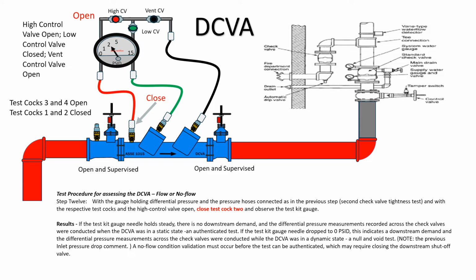Results. If the test kit gauge needle holds steady, there is no downstream demand, and the differential pressure measurements recorded across the check valves were conducted when the DCVA was in a static state. An authenticated test. If the test kit gauge needle drops to 0 psid, this indicates a downstream demand, and the differential pressure measurements across the check valves were conducted while the DCVA was in a dynamic state. A null and void test. Note the previous inlet pressure drop comment. A no-flow condition validation must occur before the test can be authenticated, which may require closing the downstream shutoff valve.